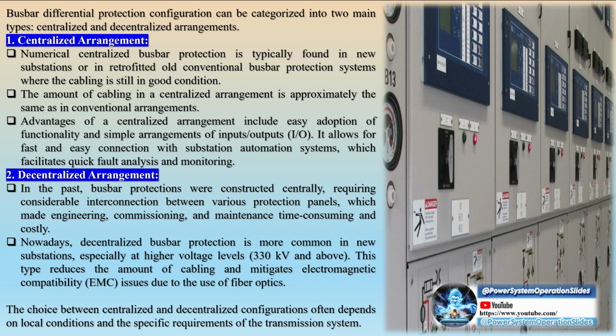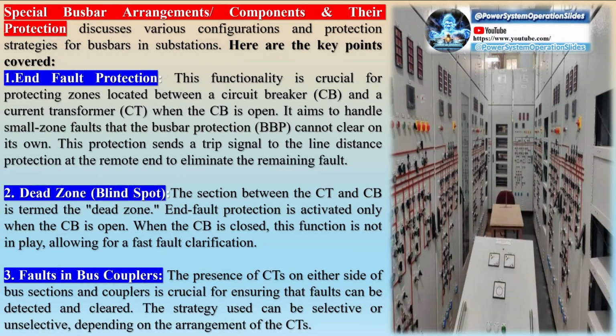While busbar protection detects these faults, tripping the CB alone does not clear them. This is managed by applying CB fail or an interlocked overcurrent relay, depending on the voltage. Circuits with end fault protection prevent busbar zone tripping for small zone faults and only intertrip the respective remote and feed end to clear the fault.